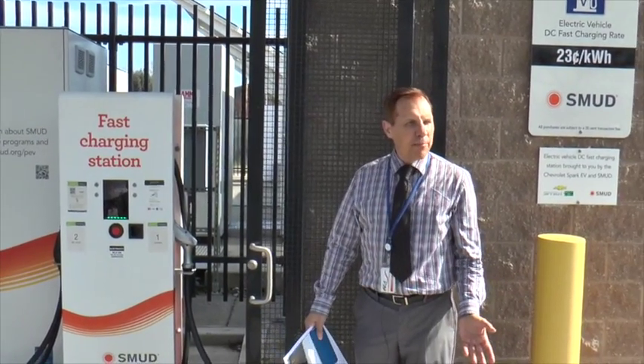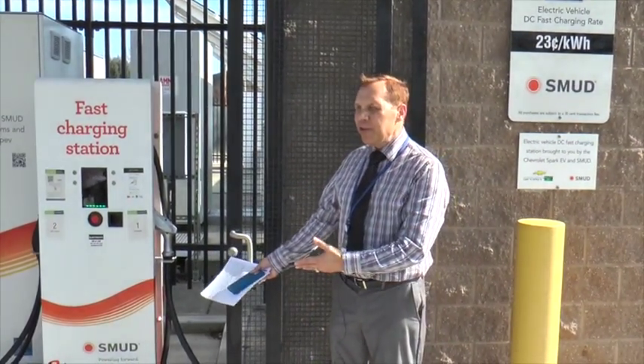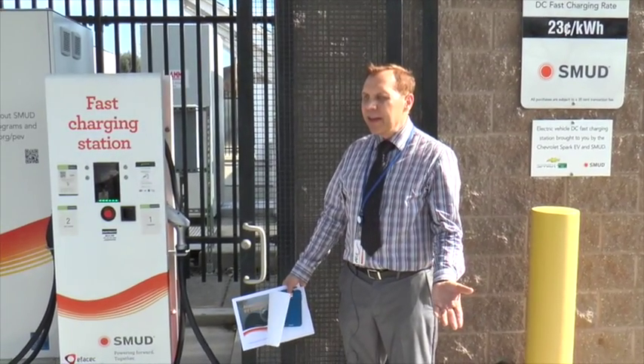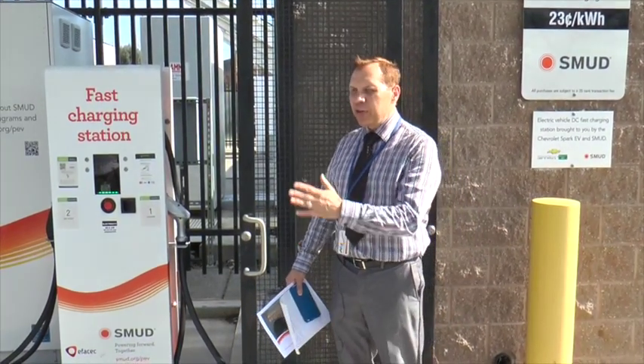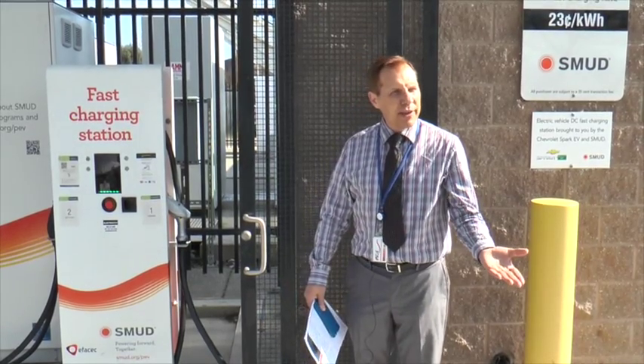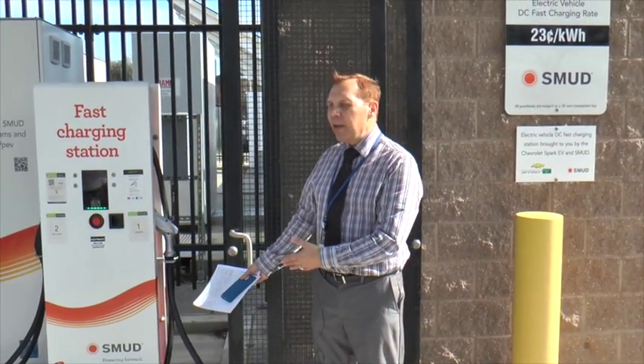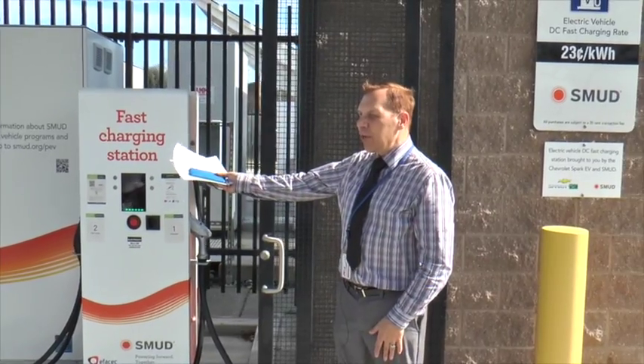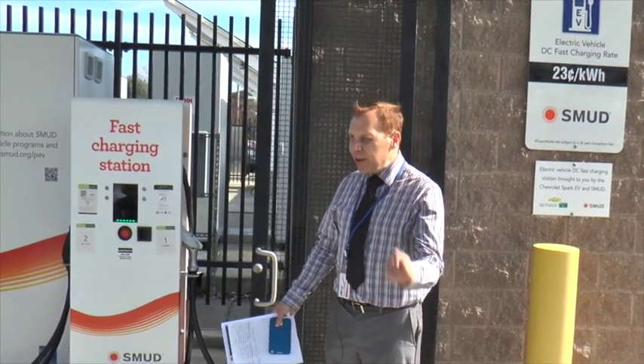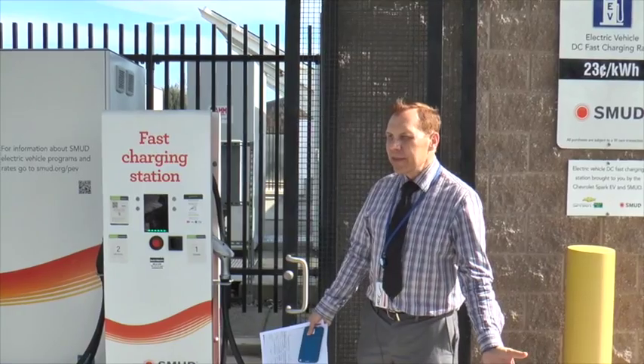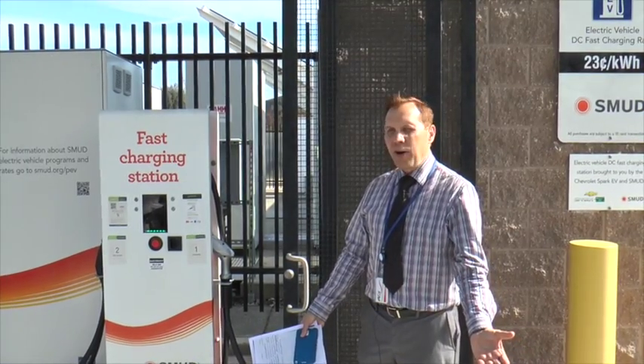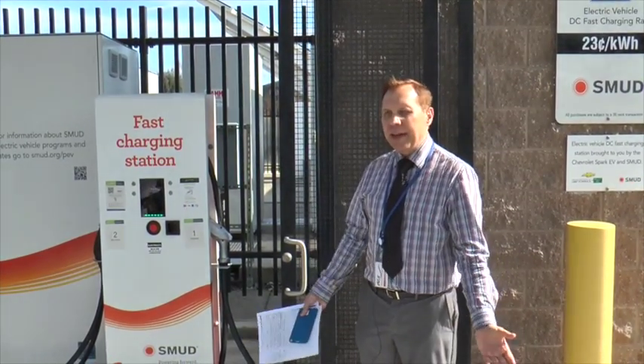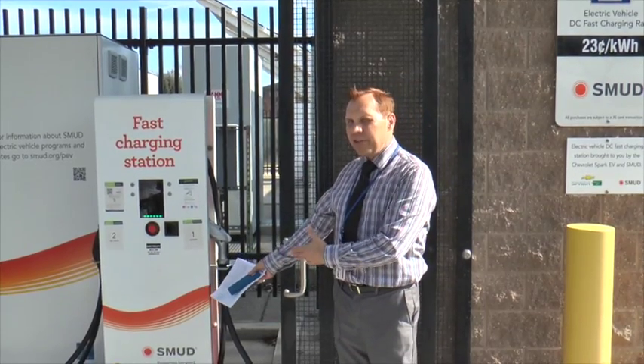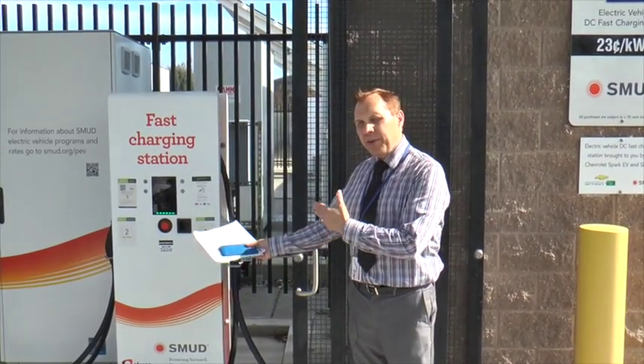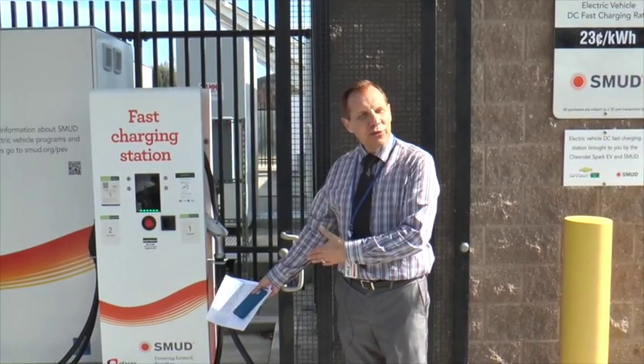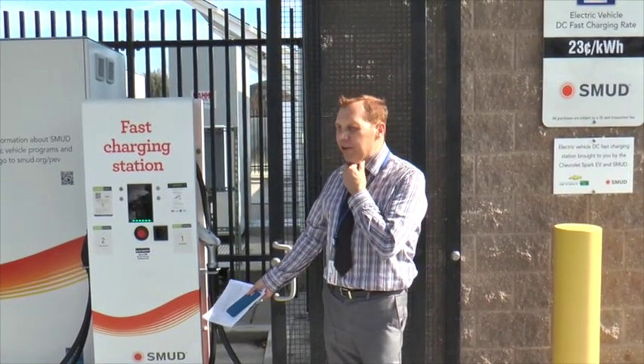They're years away from being there. As a fast charger works, we know it's DC output, and the voltage and current fluctuate with the state of charge of the battery. So how do you calibrate that? It's not like Level 1 or Level 2, where it's fixed voltage, fixed current — that's like your meter at home, fixed voltage, fixed current, we know how to do that. We don't know how to do that with DC power at varying voltage and varying amperage. So calibration of these devices is years away.